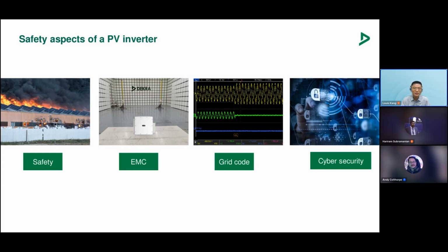Grid code not only qualifies grid compatibility and grid support ability of an inverter, but also prescribes protective functions in abnormality. Grid code concerns many safety aspects, like the safety of maintenance electricians when the grid is shut down. The grid codes are evolving quickly following the fast-growing penetration rate of renewable power generation. The quick update of grid codes deserves our close attention.